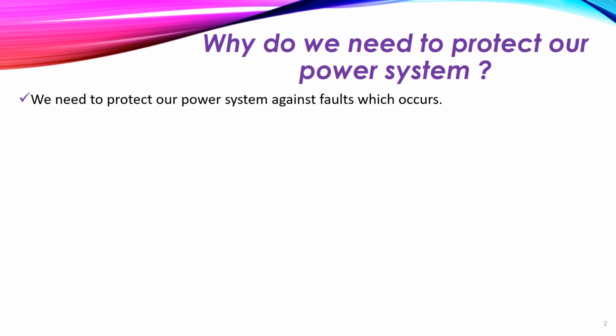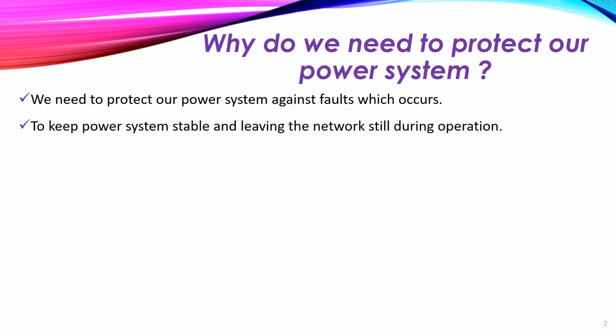These faults will affect the efficiency of our power system and the stability of our power system. So we have to expect the existence of these faults and protect our power system against the damage which will occur from these faults. Also, we need to keep our power system stable and the network live during the operation. Also, we need to clear the fault as fast as possible. So here, the time itself is very, very important in the protection of our power system.